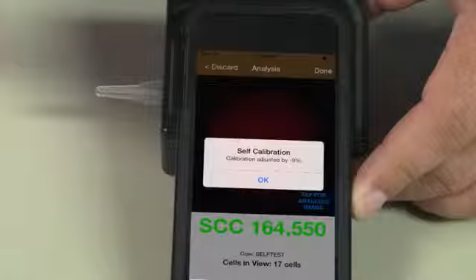From time to time, you may have to adjust the focus of the RT10. Tap the Camera app on your Apple device. Make sure the slide is inserted. You are looking for clearly defined cells. If the image is unclear, slide the Apple device back from the lens. Use a Phillips or star screwdriver to loosen the screw at the side of the device. Rotate the outer ring until optimum focus is achieved. Reinsert the camera to check. You may have to repeat the process until you get a clear image. Tighten the screw on the side when complete.